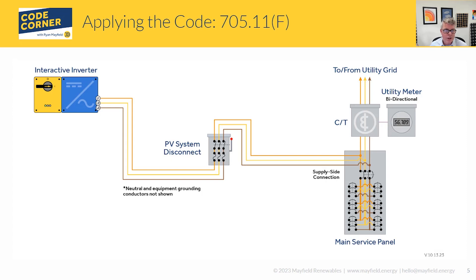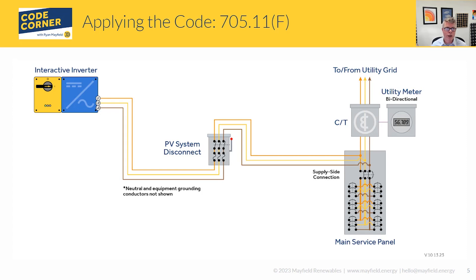Here's that image I mentioned. In the 2020 version of the code, we had this same type of graphic with a distance shown — a maximum distance between the supply side connection and the PV system disconnect, depending on residential or commercial. That's gone now in 2023. Keep that in mind when working with this, and have a conversation with your AHJ to make sure they agree on where that location is and that it's close enough to the point of connection.